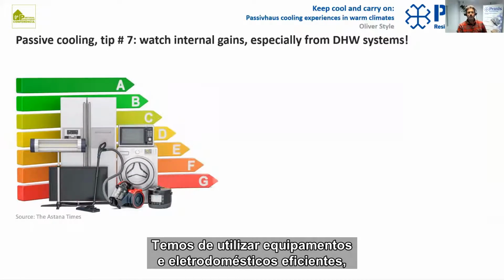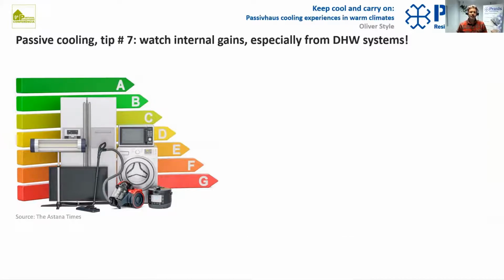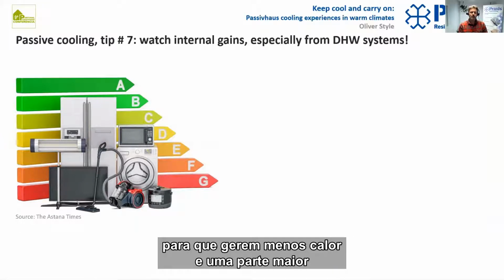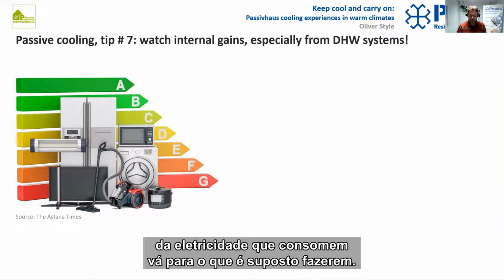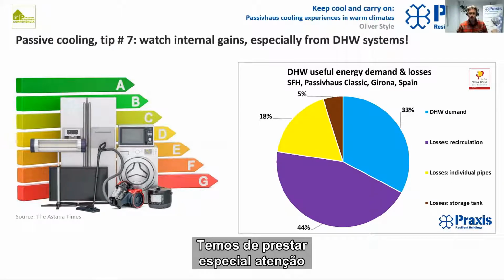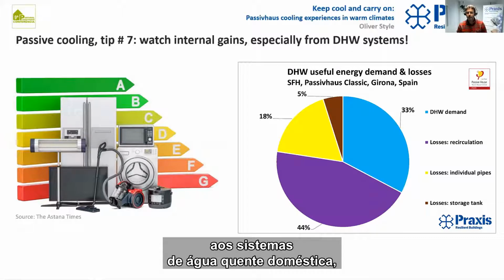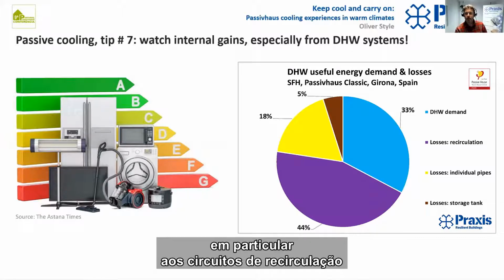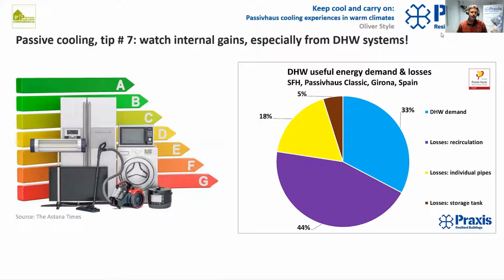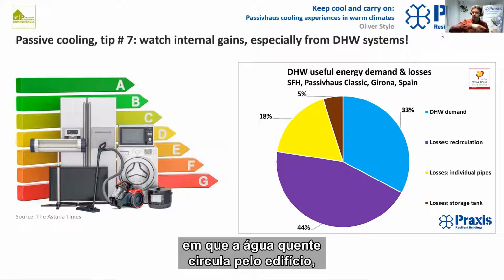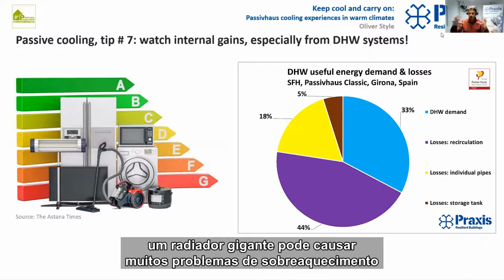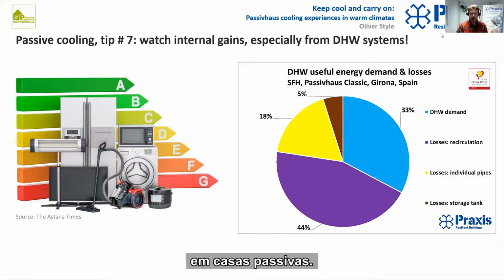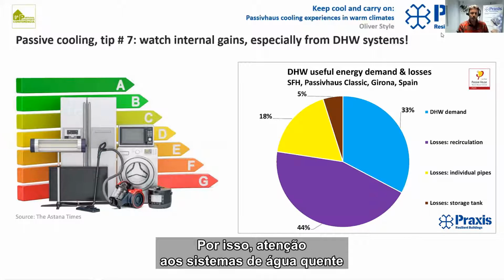Passive cooling tip number 7, internal heat gain. So we need to make sure we're using efficient equipment and appliances so that they generate less heat and more of the electricity that they consume goes towards what they're really meant to be doing. We need to pay special attention to domestic hot water systems, and in particular the recirculation loops in which hot water is circulating around a building, which can be a real killer in the summer. It can be a giant radiator which causes a lot of overheating problems in passive houses. So watch the hot water systems there.